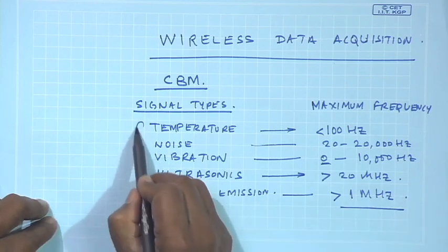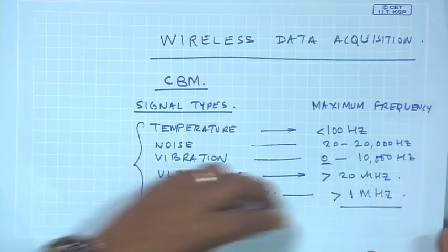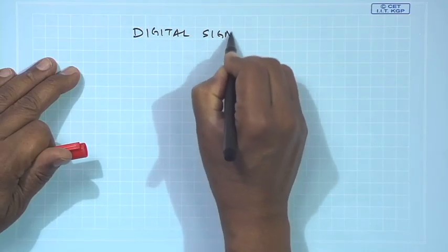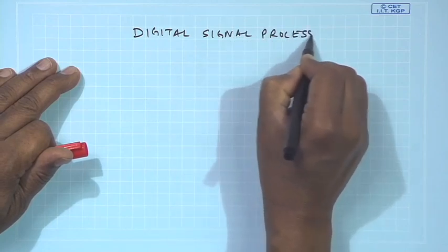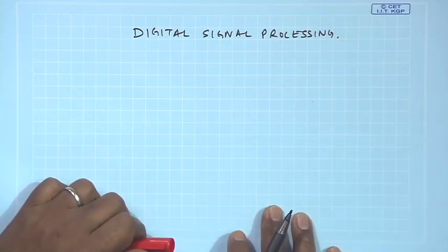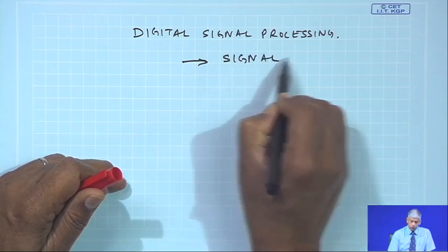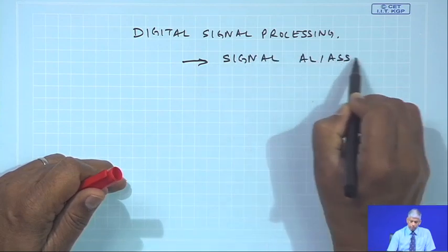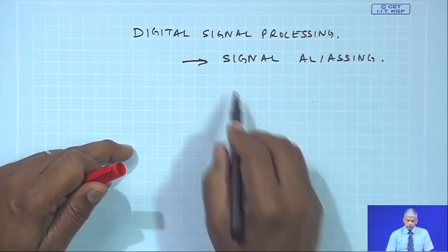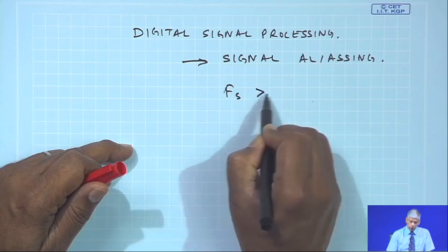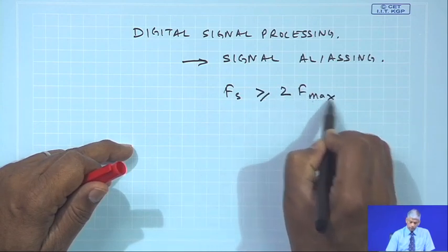In CBM we are going to come across all these signals, and at the end of the day we have to do what is known as digital signal processing. Recalling the class on computer aided data acquisition, I mentioned the condition of signal aliasing. To avoid signal aliasing, we have to have a sampling frequency which is greater than or equal to twice of f_max.